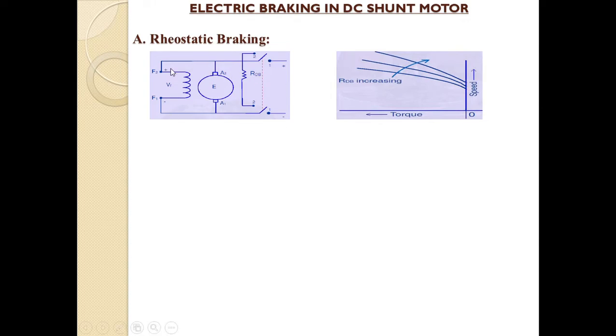Now we need to know about electrical braking in the DC shunt motor. These three types of braking are applied in both DC shunt and DC series motors. Look at the circuit diagram of rheostatic braking in a DC shunt motor — the input terminals are disconnected from the supply and connected with a variable resistance. Looking at the graph, torque is on the negative x-axis and speed on the positive y-axis. The resultant line is drawn in the second quadrant, which is called the forward braking quadrant.